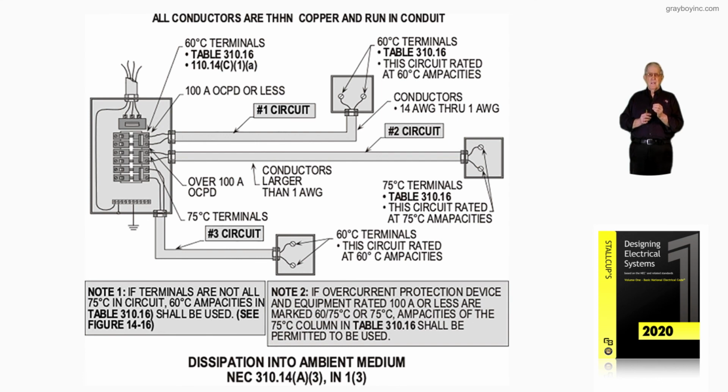So Figure 8-4 is illustrating a lot of information here identifying the dissipation into ambient media of the overheated conductors due to improperly connecting to a terminal not rated for that ampacity in accordance with 310.14(A)(3), Informational Note 1, item number 3.